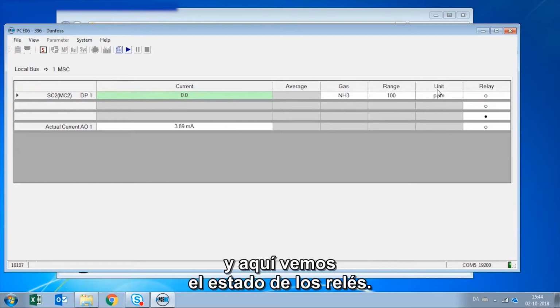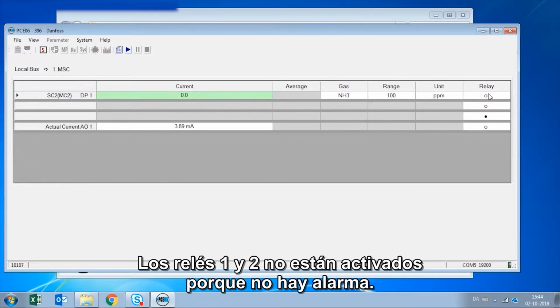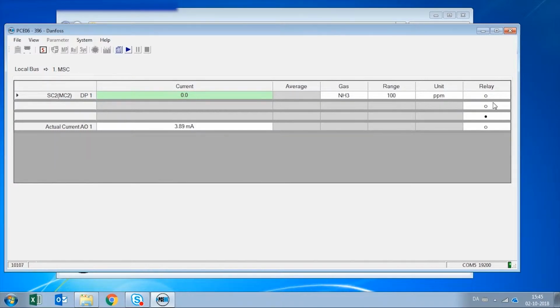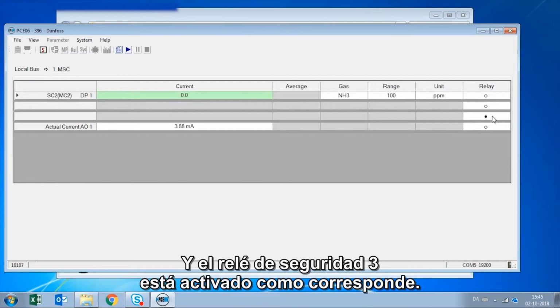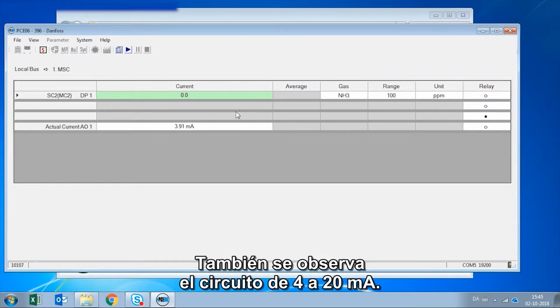And here you can see the status of the relays. Relay 1 and 2 are not energized because there is no alarm. And safety relay 3 is energized as it should be. You can also see the 4 to 20 milliamp output.